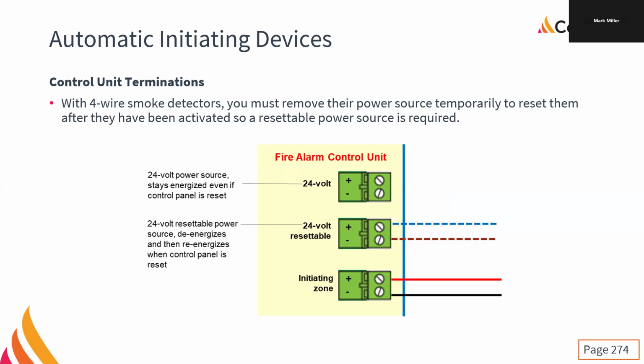When we go to connect in, the panels tend to have a whole bunch of 24-volt options for supplying power to devices. We have resettable and non-resettable 24 volts. And that's exactly what it says on the tin. When you hit the reset button, we kill the power to the resettable 24 volt. The 24 volt non-resettable, or possibly non-labeled, when you hit the reset, nothing happens. That 24 volt just keeps going. There are times that we need to use that to power things like our annunciator. We don't want to kill power to the annunciator every time we reset the panel. We want that on constant power.